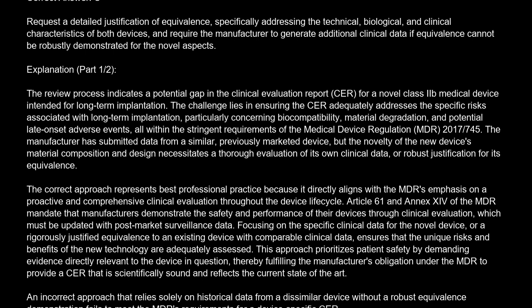Explanation. The review process indicates a potential gap in the clinical evaluation report, CER, for a novel Class IIb medical device intended for long-term implantation. The challenge lies in ensuring the CER adequately addresses the specific risks associated with long-term implantation, particularly concerning biocompatibility, material degradation, and potential late-onset adverse events, all within the stringent requirements of the Medical Device Regulation, MDR, 2017/745. The manufacturer has submitted data from a similar, previously marketed device, but the novelty of the new device's material composition and design necessitates a thorough evaluation of its own clinical data, or robust justification for its equivalence.